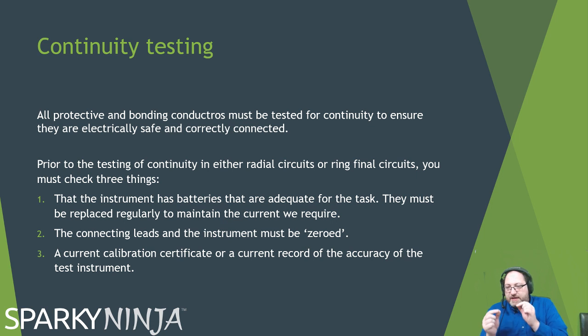So we have to actually physically take our time and actually say, right, we'll test from this supply earth to this end earth to make sure it's there. Before we do that, we've got to select the instrument. We've got to make sure that it's got sufficient battery power, and because again we're measuring accuracies that are quite low in resistance, we'll have to zero the leads or null the leads as well.